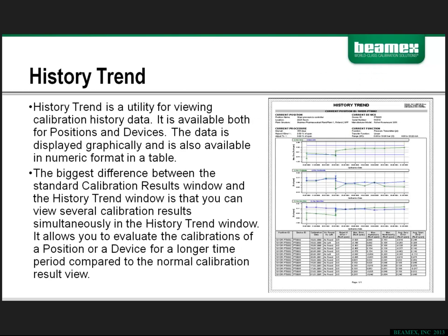So what we're looking at right now on your right-hand side is an actual history trend analysis that was done by the CMX software. And this utility is really a multitude of data. You can do it either for a position or for a particular device. And by that, a position may have multiple devices over a particular period of time. You can look at all of those together, or you can look at them individually. You can see in the middle section, the data is displayed graphically, and then down at the bottom, it's displayed numerically, so that you can see the trend visually, and then look at the calibration actions individually to determine where the most gross error may have been for a particular device.